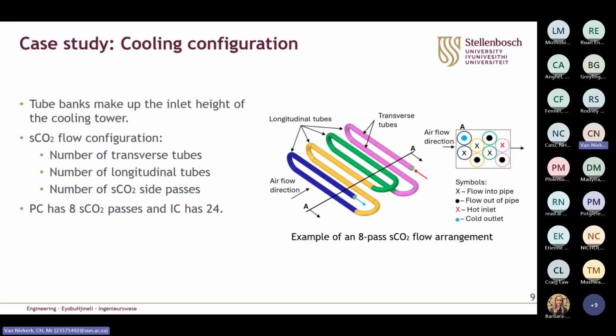So for the SCO2 flow arrangement, each individual tube bank makes up the total cooling tower inlet height, where the same circular fin tube heat exchanger is stacked on top of one another. In this case, the SCO2 flow arrangement approximates a multi-pass cross-counterflow heat exchanger to ensure that there's a larger temperature difference between the air side and SCO2 side. So the flow configuration is made up of a number of transverse tubes along the height of the tube bank and a number of longitudinal tubes along the airflow direction, which in total makes up the total SCO2 flow passes.